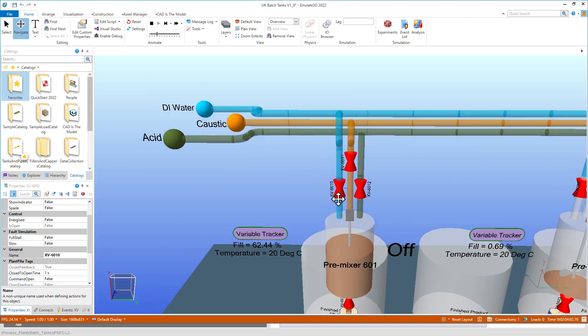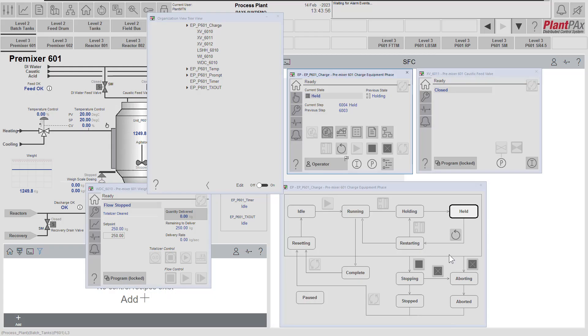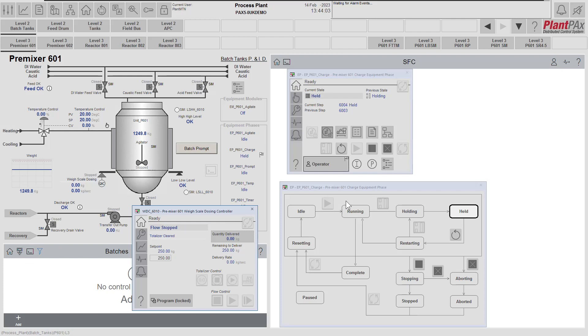As you can see, that command was sent down, the valve reset, and everything has now returned to healthy. The phase is still in the hold state and we need to send it a restart command to go back into restarting, to get everything back into a good state and then running. But if we don't fix the valve, it will not open and we'll be back in the same place. So let's go and fix the valve in our Emulate 3D model by removing the false stall fault. We'll go back into our operator workstation and then restart the phase.